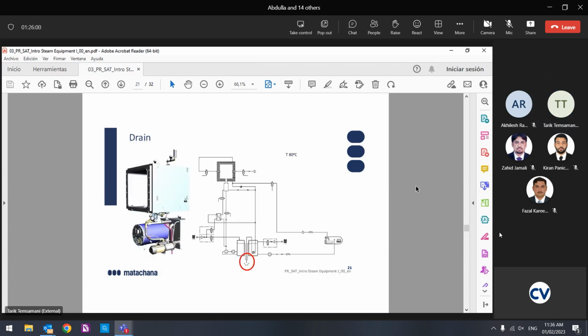Yes. Then we have the last one, the drying. We also have models without a steam generator. Yes, if the hospital has a steam line, you can use the steam line from the hospital directly. Right, it is cheaper and has less electricity consumption. Then the drying: we only need that the material we use can support this temperature, basically. I'm talking about the drying in the hospital, on the floor. Of course, because the drying comes from the machine, they have to support 80, 90 degrees. That's enough.